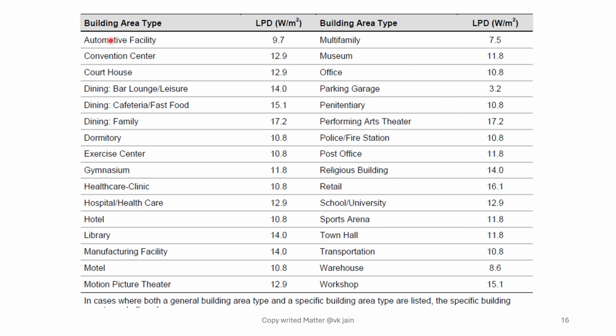And ECBC building, any building which is having 1,000 square meter of air conditioned area or having a load requirement of 125 kilowatt is called ECBC building. And in all ECBC buildings, the different parts of the building should not have lighting power density more than that prescribed in the second and fourth column. Now you can look, for office buildings, it is 10.8. So the sum of total office requirement must not be more than this lighting power density multiplied by the square meter area of that particular building.